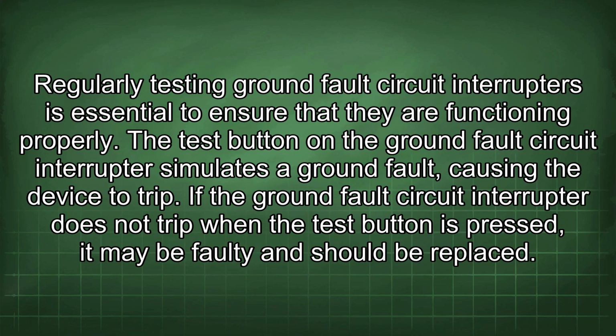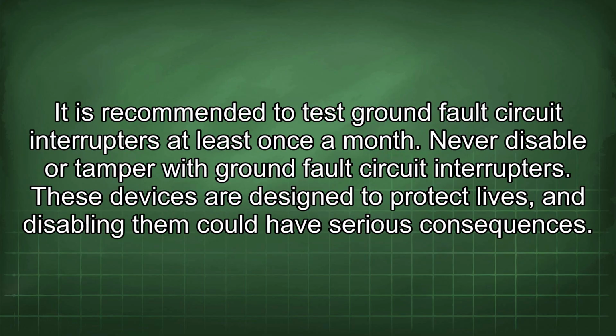Regularly testing ground fault circuit interrupters is essential to ensure that they are functioning properly. The test button on the ground fault circuit interrupter simulates a ground fault, causing the device to trip. If the ground fault circuit interrupter does not trip when the test button is pressed, it may be faulty and should be replaced. It is recommended to test ground fault circuit interrupters at least once a month. Never disable or tamper with ground fault circuit interrupters. These devices are designed to protect lives, and disabling them could have serious consequences.